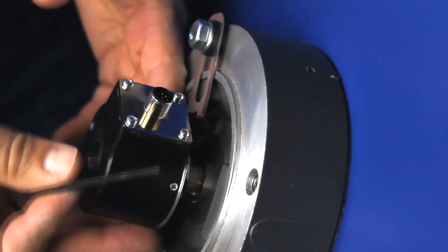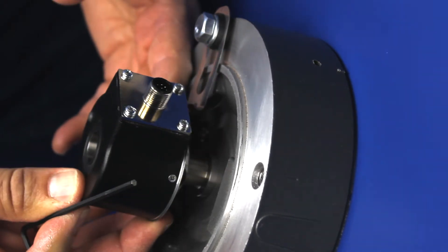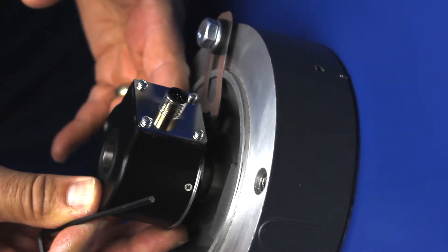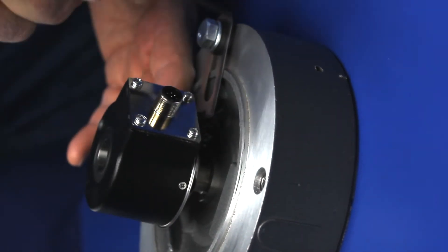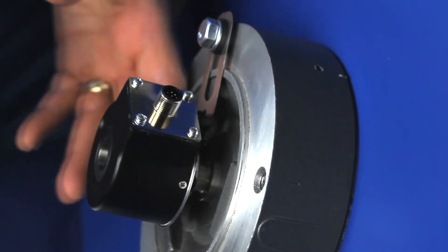Adjust the encoder axially to its final location on the shaft. Ensure that the flex arm is straight, not bowed, otherwise you can apply unnecessary loads to the encoder bearings.